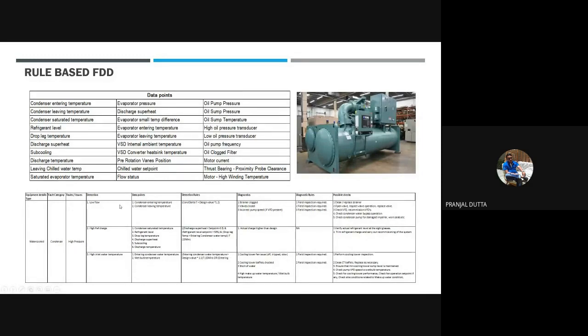For condenser high pressure, detections will be done at three levels: low flow, high refrigerant charge, and high inlet water temperature. These are the main reasons for high pressure in the condenser. Then you have to find out which data points are connected. For low flow, the entering water temperature and leaving water temperature can be used to calculate the flow. If your flow is low, then your delta T will be high. If flow is high, delta T will be low. From there, you can find out that your flow is low. Then for the refrigerant level, you can take these data points to calculate the fault in the refrigerant level.